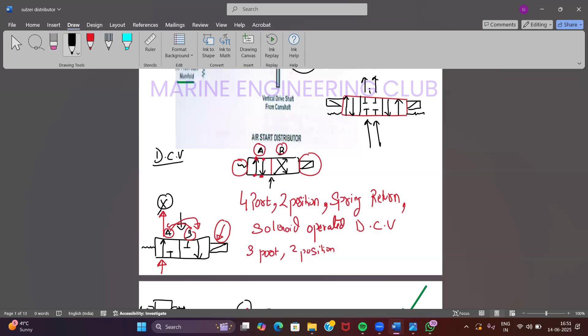A, B, and C. So normally it will be connected like this. If this solenoid valve gets activated, this C will go onto the B side and B will come onto the A side. Then how the inlet and outlet will be? This will become return and this will become inlet. Agreed? Similarly, if I energize my A side, and as soon as I disengage or don't give supply to my solenoid, this spring will return back positions of ABC. That's why it is known as spring centered.